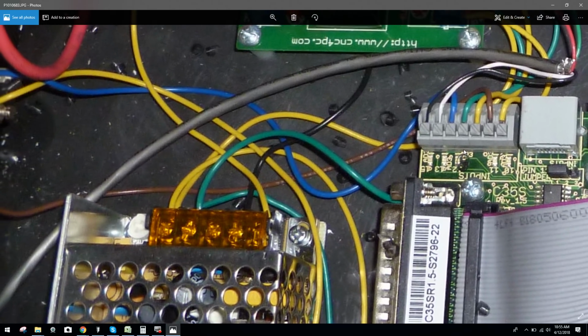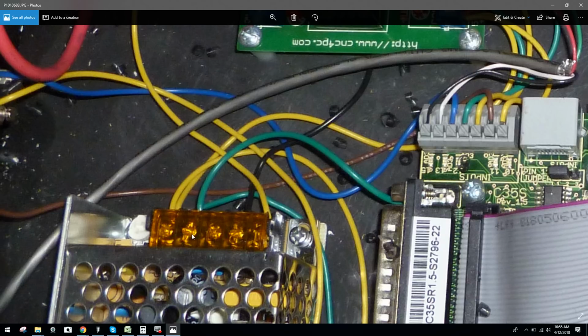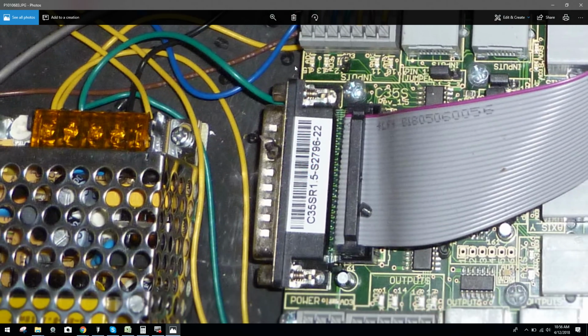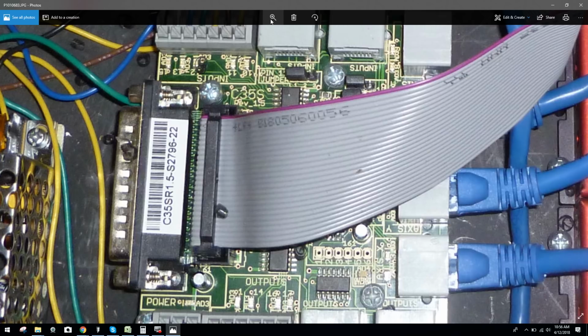Okay? As we come over here, we have a 5-volt power supply. 5-volt power supplies, again, are low voltage. Low voltage means even more susceptibility to EMI. And as we look at this, you can see we have two leads coming in here to this terminal, once again, daisy chaining to get the job done and get the job out the door so they can make their money. And this is not the correct way to do this. There should have been, once again, a splitter block, one terminal coming over from the power supply, use your splitter block, and actually come over here and wire the remaining leads that need to be incorporated in the system. Okay? Can't come over here yet. We'll zoom out.